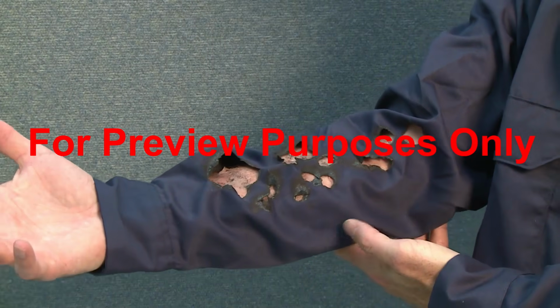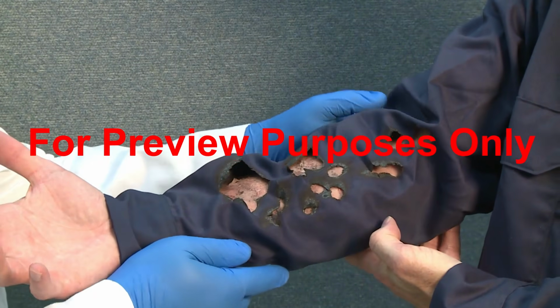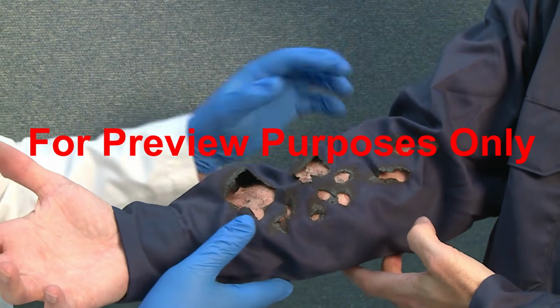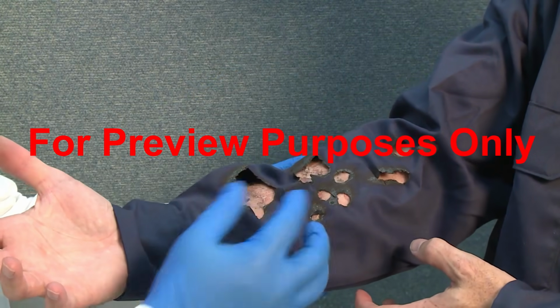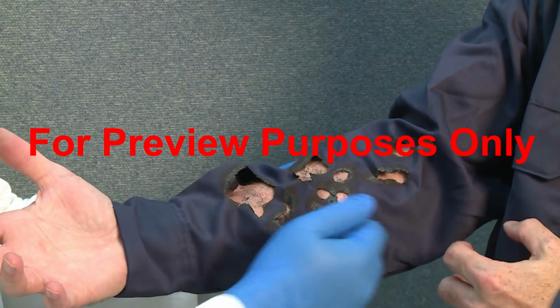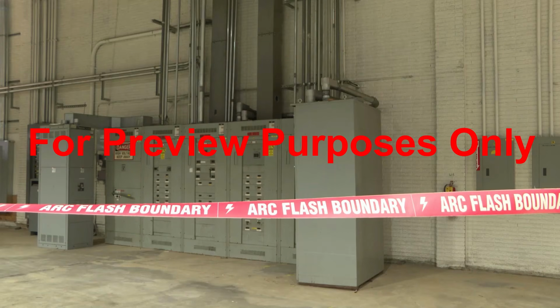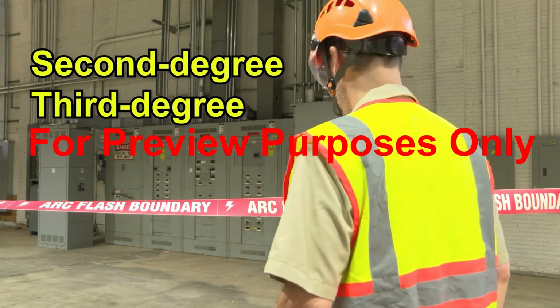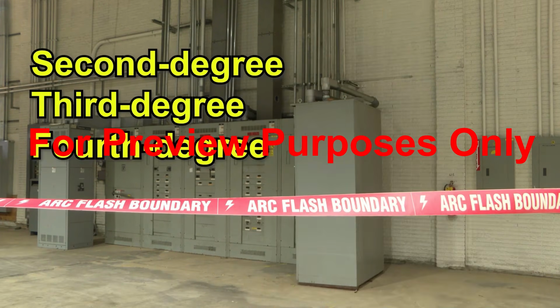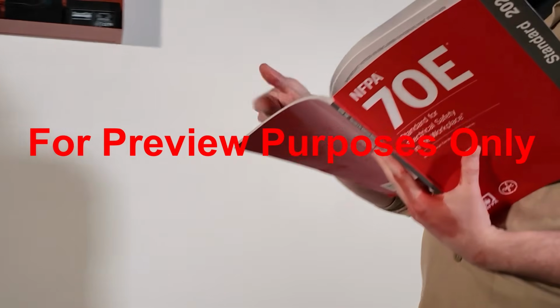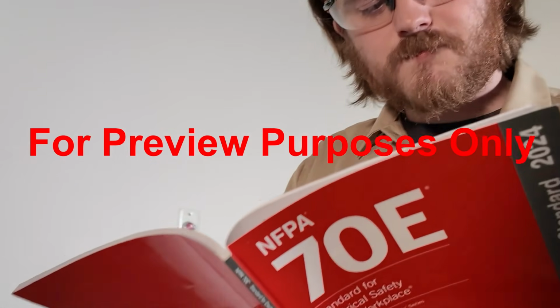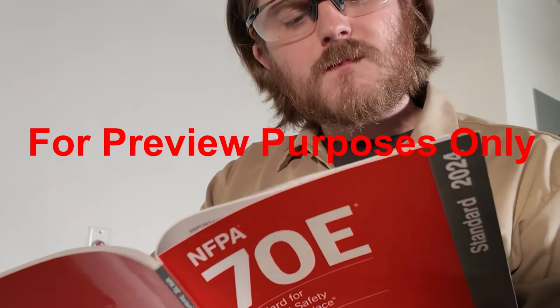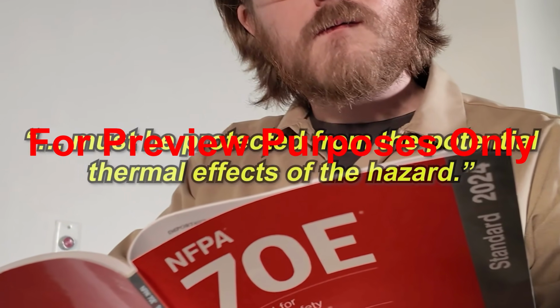Although you can still experience an arc flash burn from outside the arc flash boundary, the burn is less likely to be as severe as a burn that occurs within the boundary. Once you cross the boundary, you're more likely to suffer second, third, and even fourth degree burns in the event of an arc flash. So NFPA 70E states that any body part that crosses into the arc flash boundary must be protected from the potential thermal effects of the hazard.